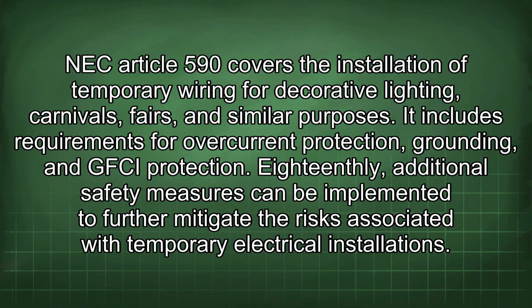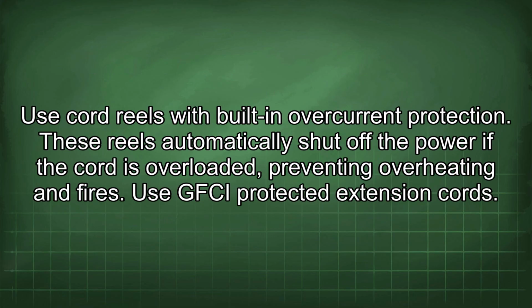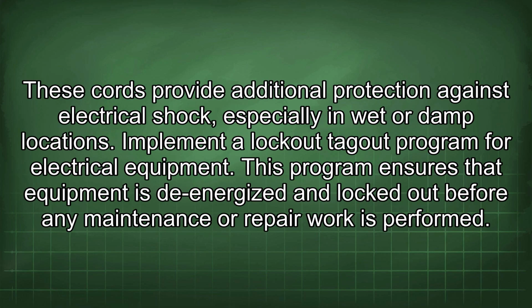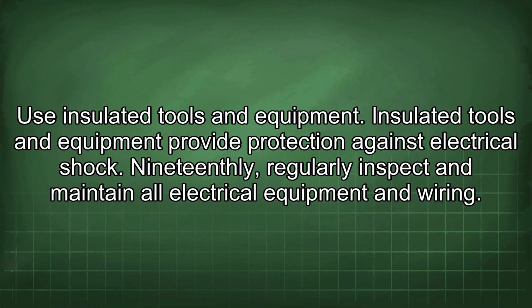18thly, additional safety measures can be implemented to further mitigate the risks associated with temporary electrical installations. Use cord reels with built-in overcurrent protection. These reels automatically shut off the power if the cord is overloaded, preventing overheating and fires. Use GFCI protected extension cords. These cords provide additional protection against electrical shock, especially in wet or damp locations. Implement a lockout-tagout program for electrical equipment. This program ensures that equipment is de-energized and locked out before any maintenance or repair work is performed. Use insulated tools and equipment. Insulated tools and equipment provide protection against electrical shock.